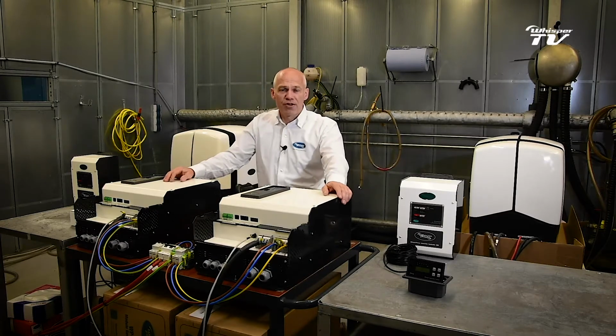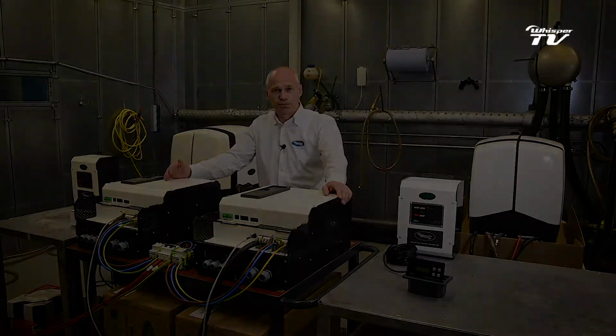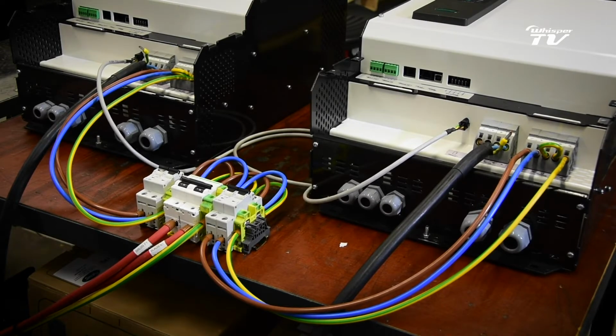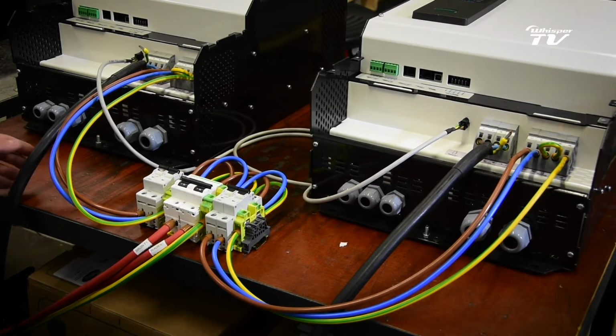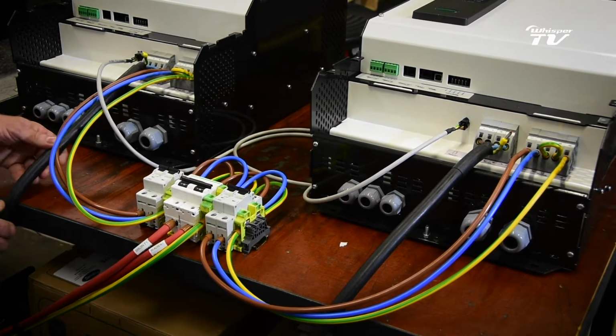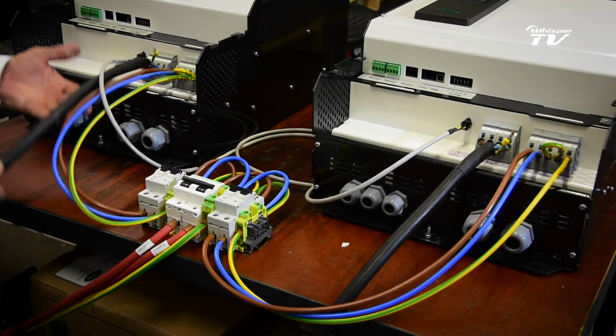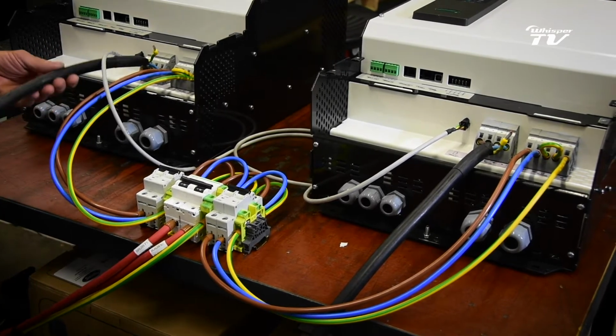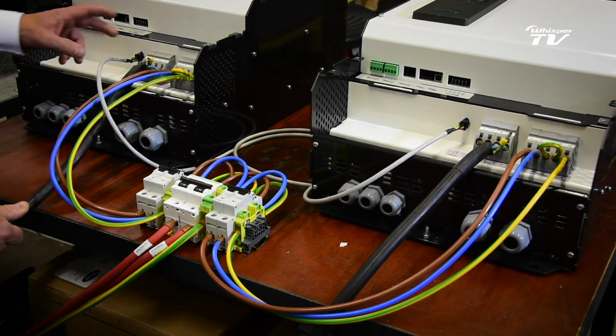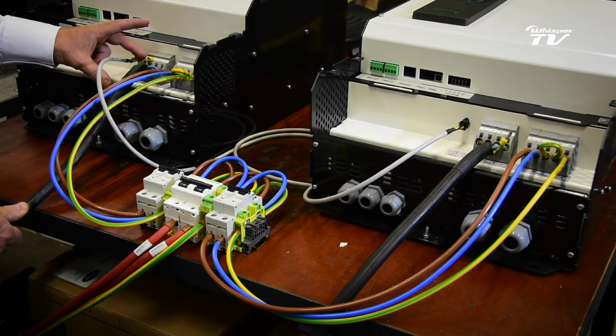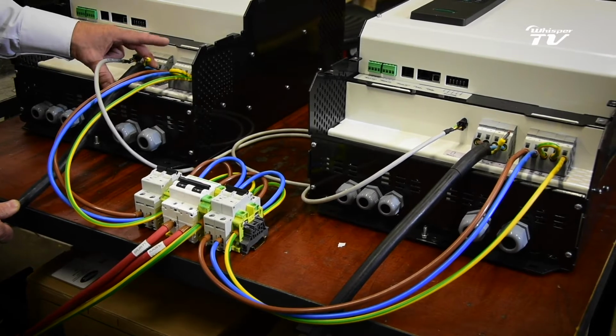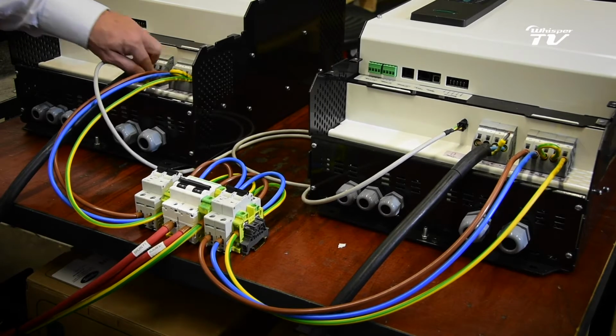Let me demonstrate how the system actually works. Alright, well here we have the overview of the two inverters. Each inverter is connected to the WhisperPower Genverter power generation. So we will have a 5-wire cable coming in from the 15 kVA WhisperPower generator: phase 1, 2, 3, a neutral connection and a ground connection.